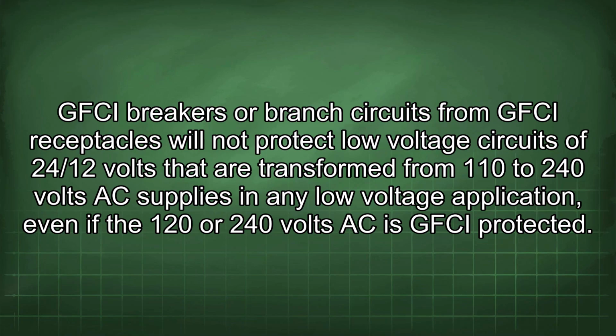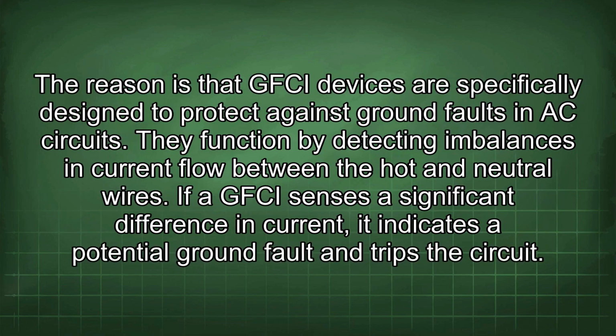GFCI breakers or branch circuits from GFCI receptacles will not protect low-voltage circuits of 24/12 volts that are transformed from 110 to 240 volts AC supplies in any low-voltage application, even if the 120 or 240 volts AC is GFCI protected. The reason is that GFCI devices are specifically designed to protect against ground faults in AC circuits. They function by detecting imbalances in current flow between the hot and neutral wires. If a GFCI senses a significant difference in current, it indicates a potential ground fault and trips the circuit.